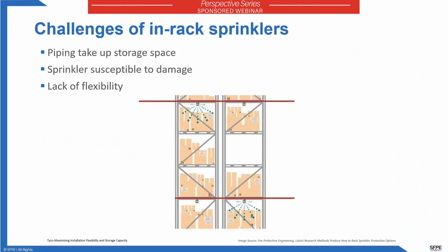Now, you might be saying, well, why do I always want ESFR sprinklers? I'm sorry, ceiling only protection. What's the benefit of ceiling only protection? Because there's an alternative thing you can do if you want to have good fire protection, and that's you could use in-rack sprinklers. So in-rack sprinklers, as the name implies, are taking sprinklers and installing them right within the racks.